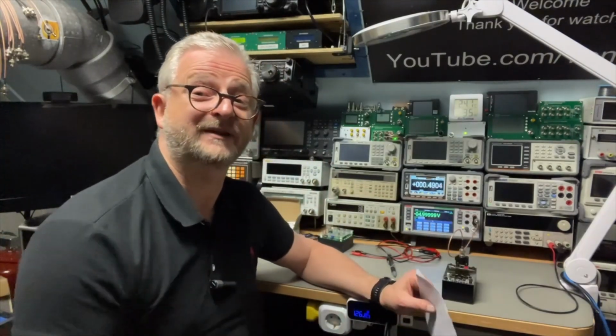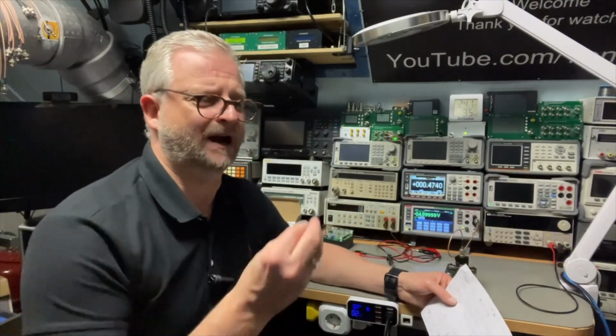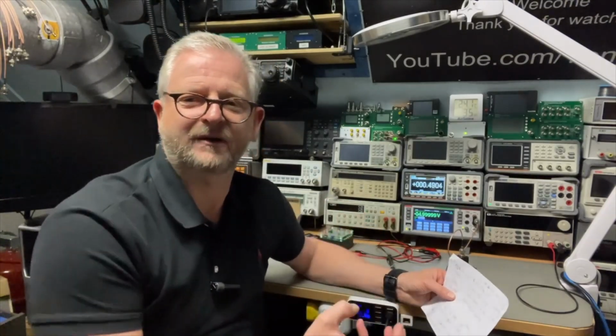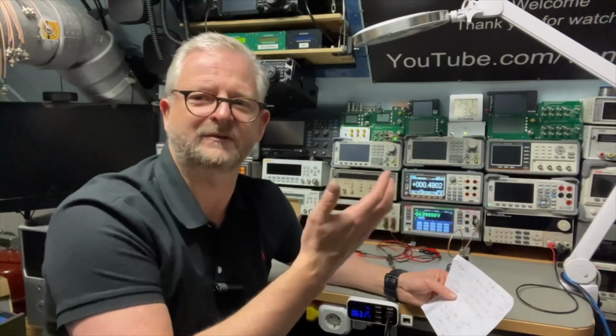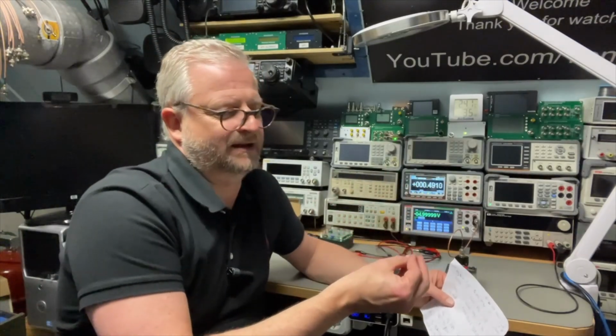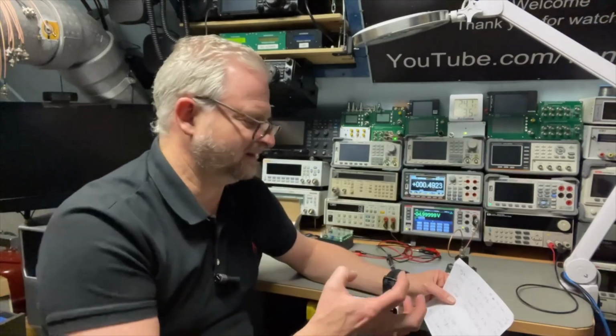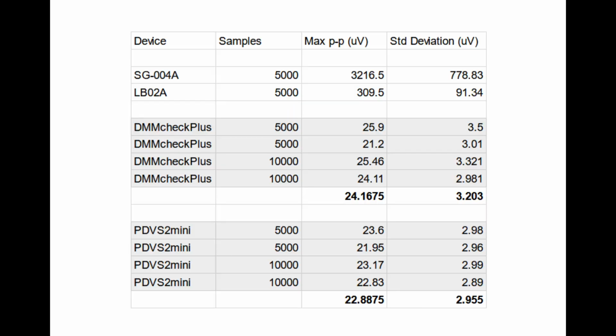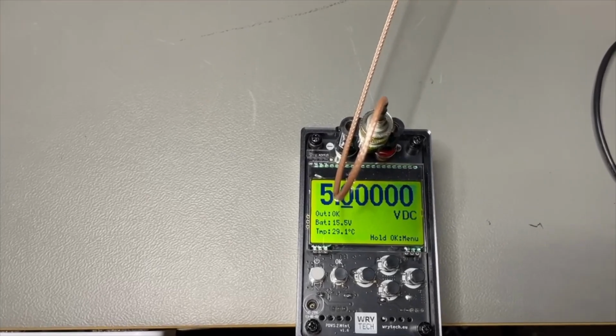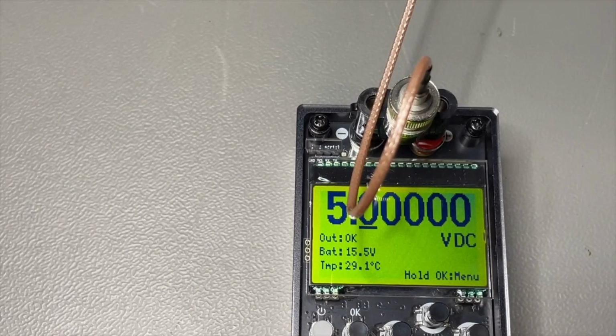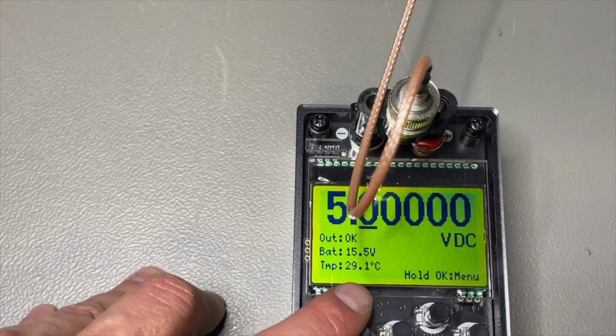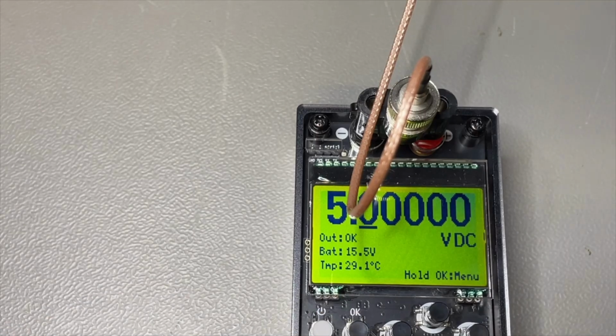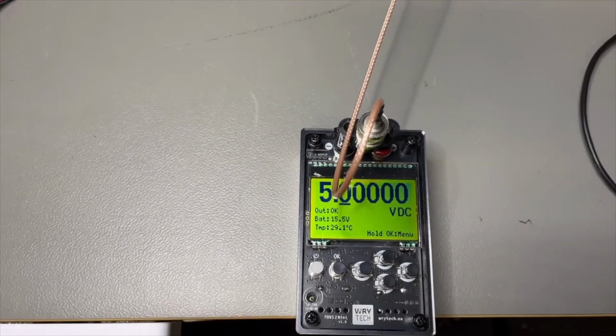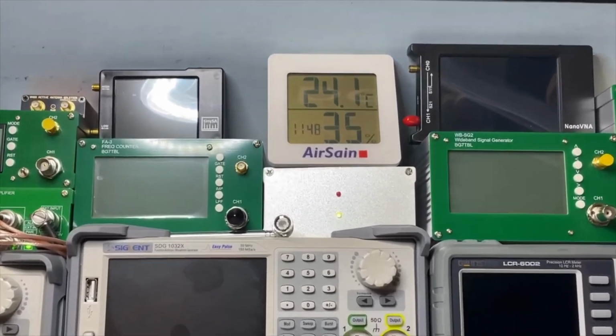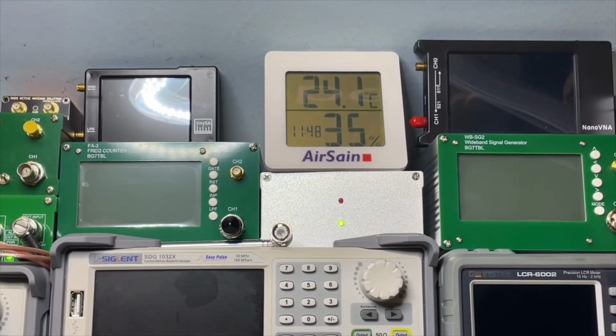I did a test with 5,000 samples and with 10,000 samples. I tried with a little bit higher impedance and a bit lower, so the automatic mode should give me 1 gig or 10 gig, and with the standard 10M, but they didn't change the values. The temperature, it's been on now I think for 2 hours. Inside it is 29.1 and the calibration was done at 29.3, so that is good. The lab has gotten warm and we are around 24. It's actually a little bit high, but let's see what the values do now.